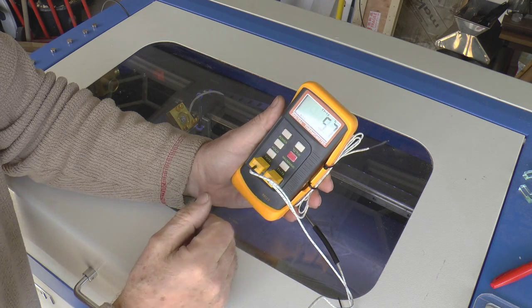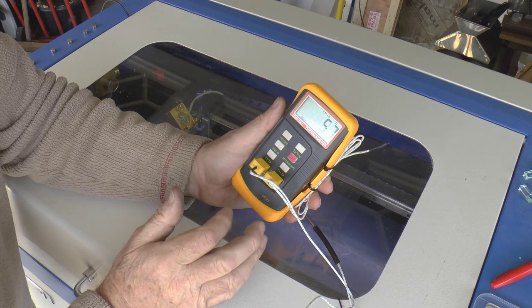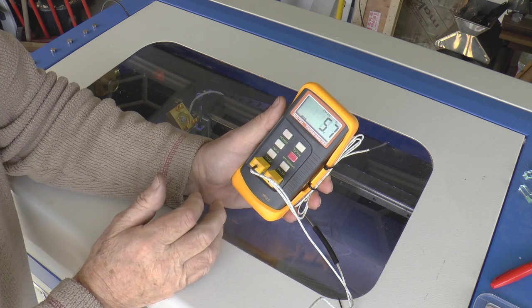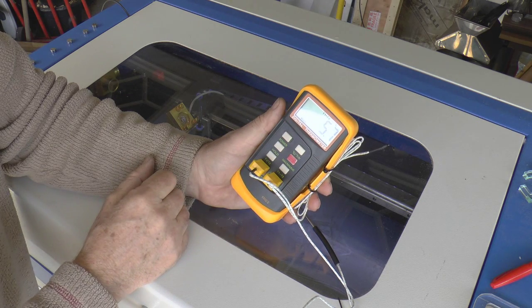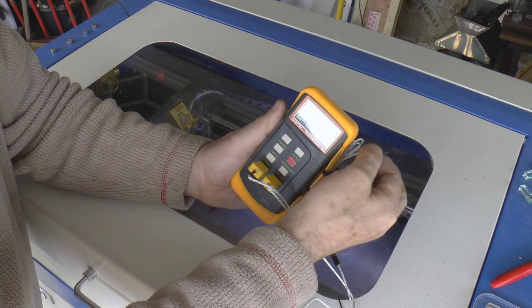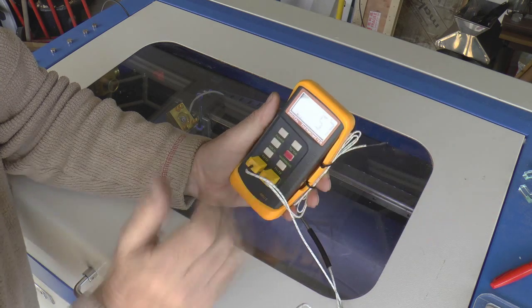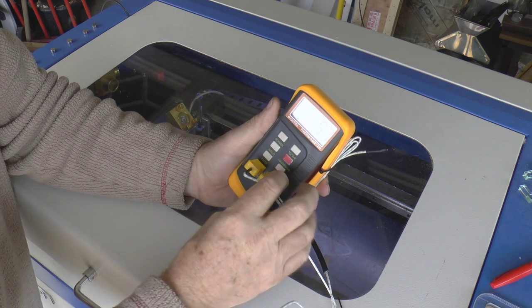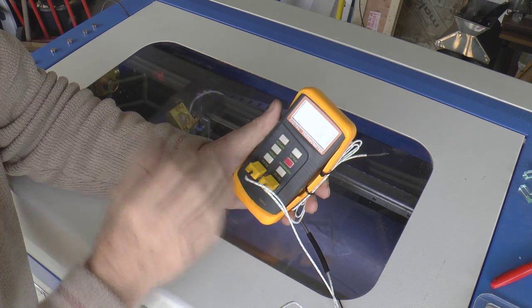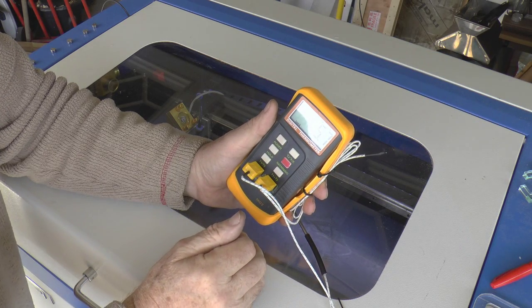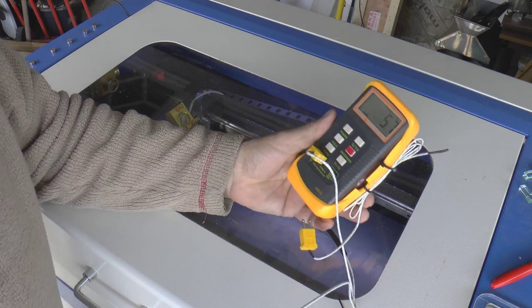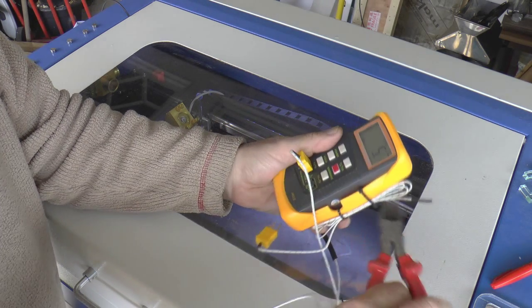So something changed with the ambient after we looked at it, and that's the problem. It's a great idea because it means you don't have to remember anything - all you need to do is use that button to do your subtraction for you. But the problem is you can't guarantee that this is measuring exactly ambient, because you could put your hand near it and it could be picking up anything. So I'd suggest you actually don't. I've experimented with this, and because you've got two sensors, you've got two possible errors, plus this additional error that can occur because of ambient changes before you take your test. Although in principle it's a great idea, it's going to possibly give you inaccuracies in your results.